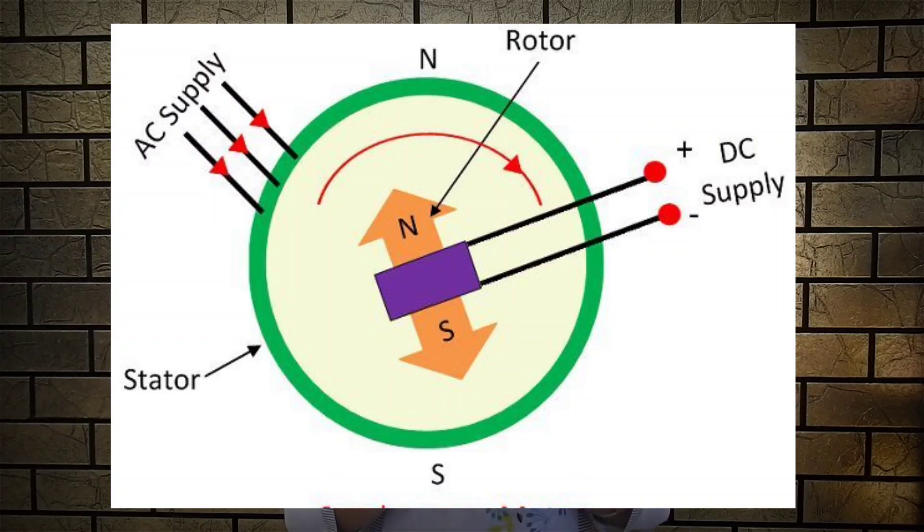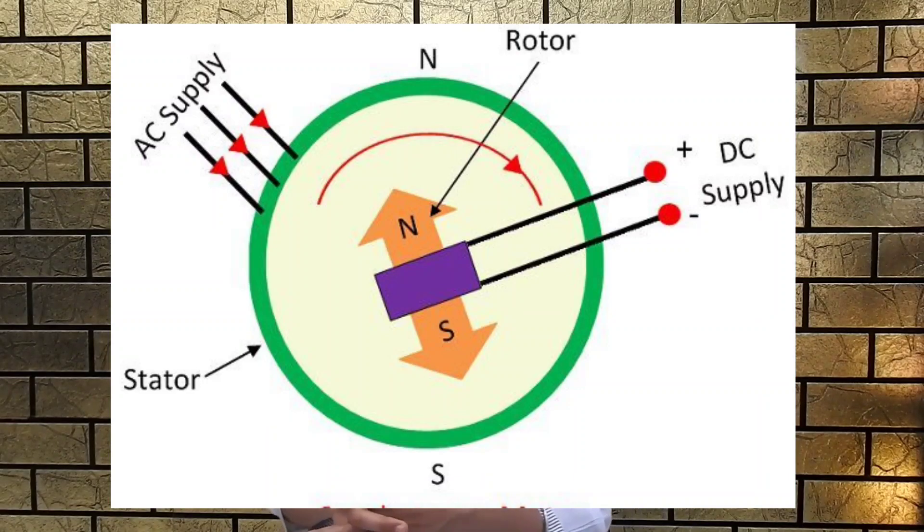The synchronous motor works with two electrical inputs. The stator is equipped with a three-phase AC supply while the rotor is provided with DC supply. The stator winding generates a three-phase rotating magnetic flux and the rotor carrying DC supply produces a constant flux. At a particular instant the rotor and stator poles might be of the same polarity — north to north and south to south — causing a repulsive force, and at the next instant it will be north-south causing an attractive force. Due to this alternating attractive and repulsive force, the motor cannot rotate and remains in a standstill position.